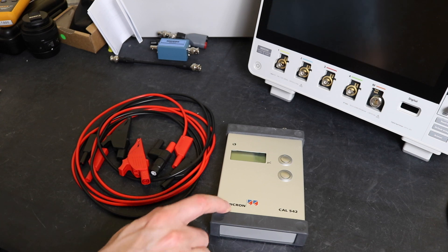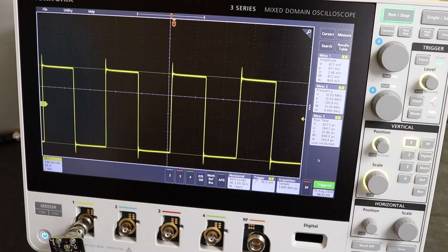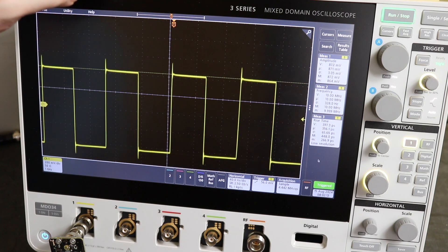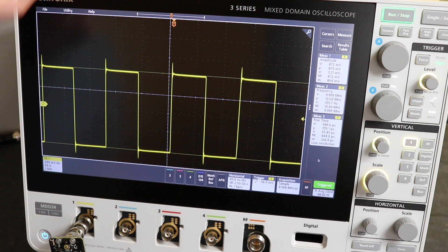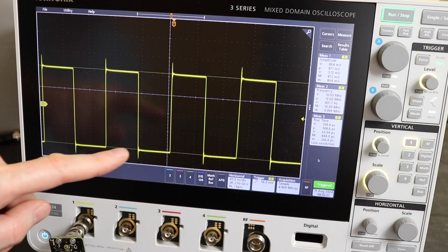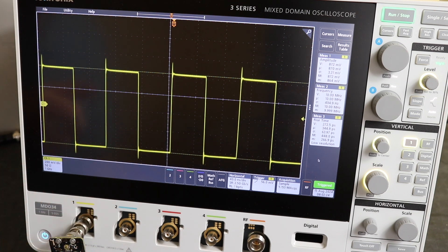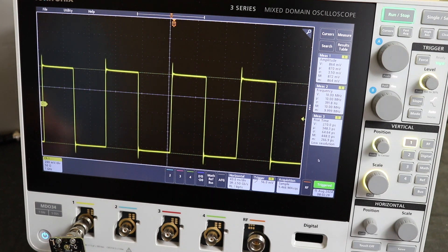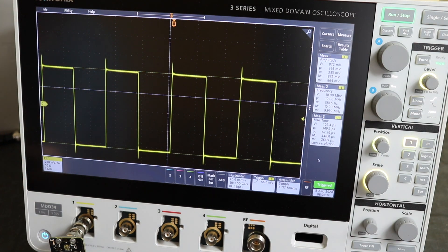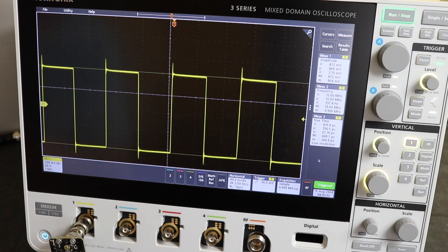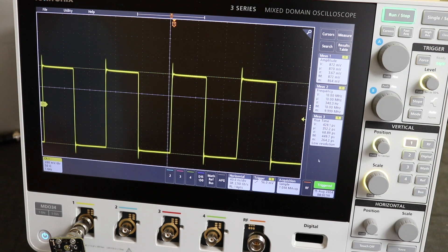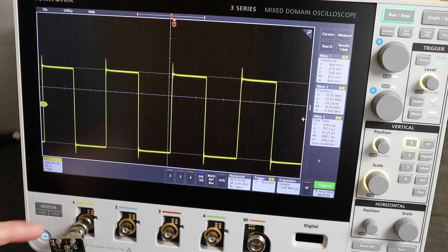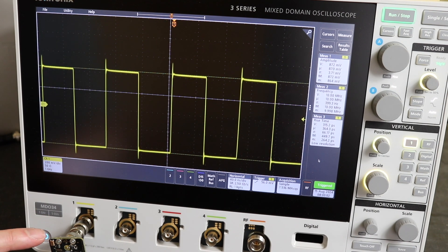Because my intention is to actually carry out a calibration on the unit, while the scope here does have an independent calibration, prior to actually taking the measurements on the Omicron unit I do run a test signal through the scope just to verify what's going on with it and I record the readings from that. That can act as another baseline. In future when I take measurements I can repeat this test just before just to make sure that everything is running okay with the oscilloscope. It's just a precautionary measure to give me a bit more credibility to the measurements I am making. The unit that I'm using to inject the signal is down here in the corner.